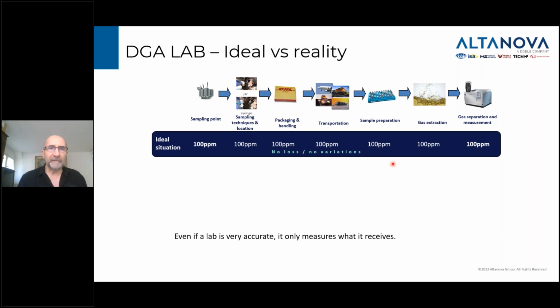So let's look at a different way of doing DGA. Since the mid-1960s, when DGA became standard around the world for transformers, the process, especially for the lab, is very lengthy. You go to the sampling points, taking different types of sampling techniques and locations. Usually the majority of people try to use the drain valves, using syringes or containers. Then usually the product is packaged and sent, sometimes to a very close area where the sample has been taken, sometimes very, very far, depending on the geography of the country and where the DGA labs are.